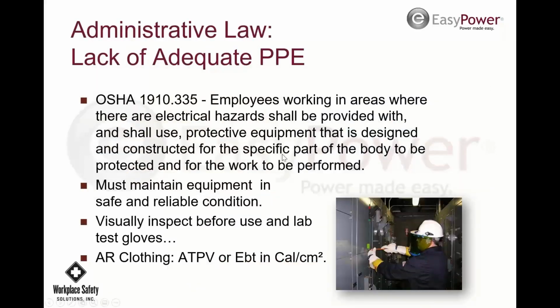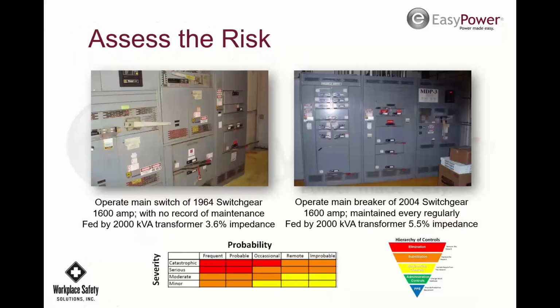Lee, we got a couple other questions in this area. Yeah. Would you recommend layering FR clothing, especially when you're switching? I would recommend layering when it's required to be layered. So assess the hazard, know what the arc flash level is. If I have an arc flash level, I have a label, the engineering study's been done, the label says 16.6 calories, I'm going to layer up to beyond 16.6.